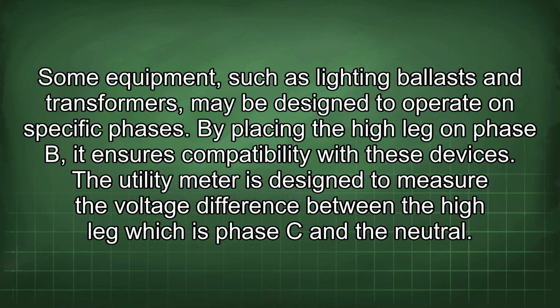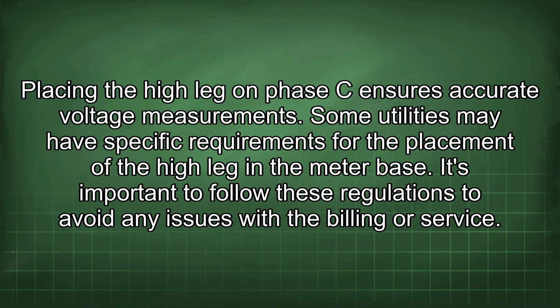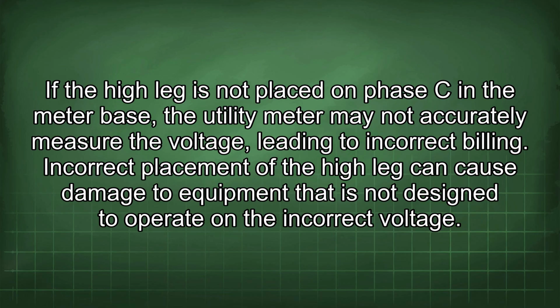The utility meter is designed to measure the voltage difference between the high leg, which is phase C, and the neutral. Placing the high leg on phase C ensures accurate voltage measurements. Some utilities may have specific requirements for the placement of the high leg in the meter base. It's important to follow these regulations to avoid any issues with the billing or service. If the high leg is not placed on phase C in the meter base, the utility meter may not accurately measure the voltage, leading to incorrect billing.